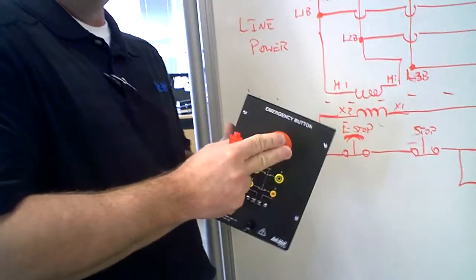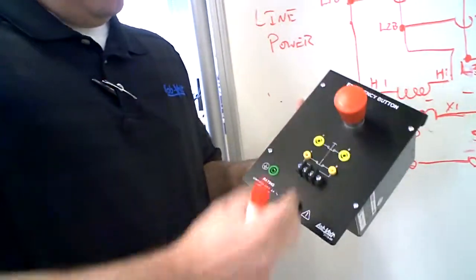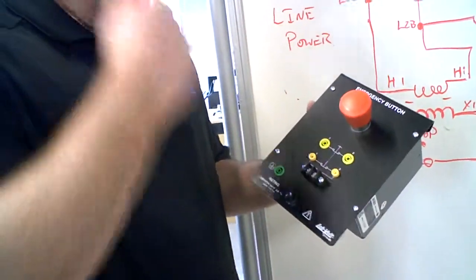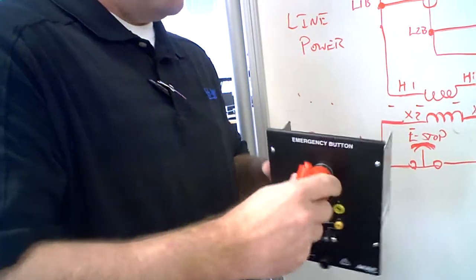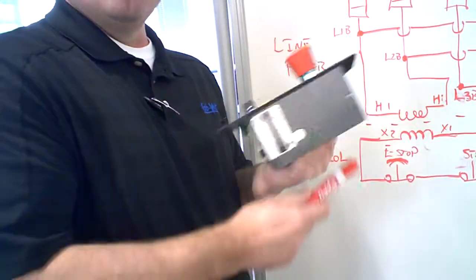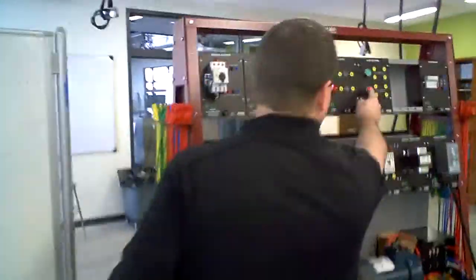So this is a mechanical latching switch. Push to reset, or twist to reset. It is maintained contact, open and close. This is there to protect you in the event something happens. And the reason that this is designed the way it is, with a mushroom head or where it's fully accessible, as opposed to using this as a stop button.